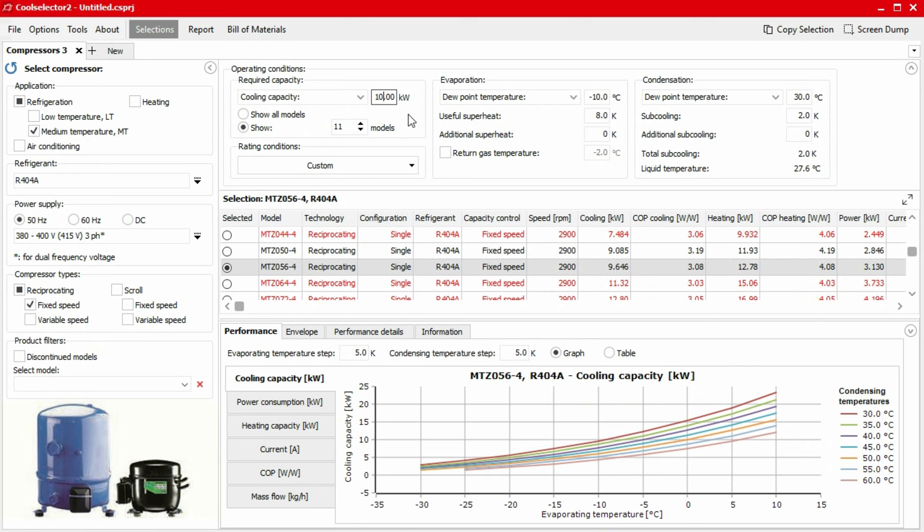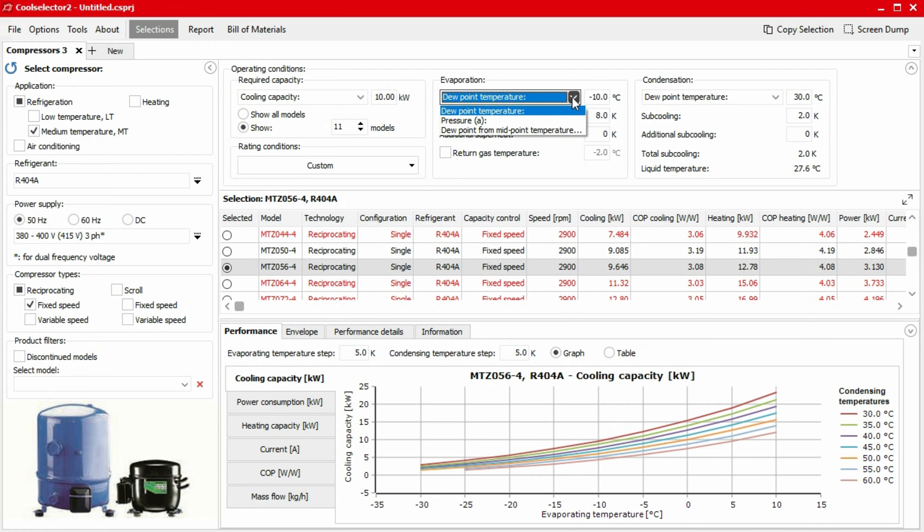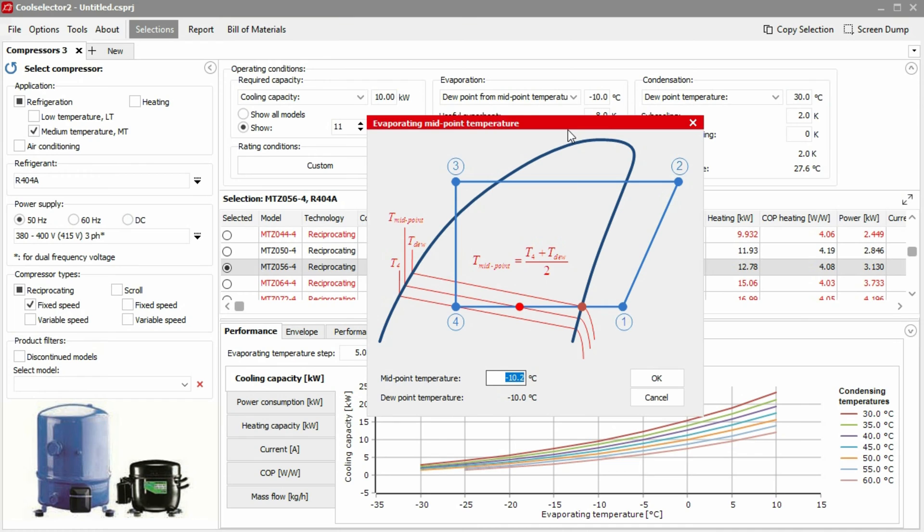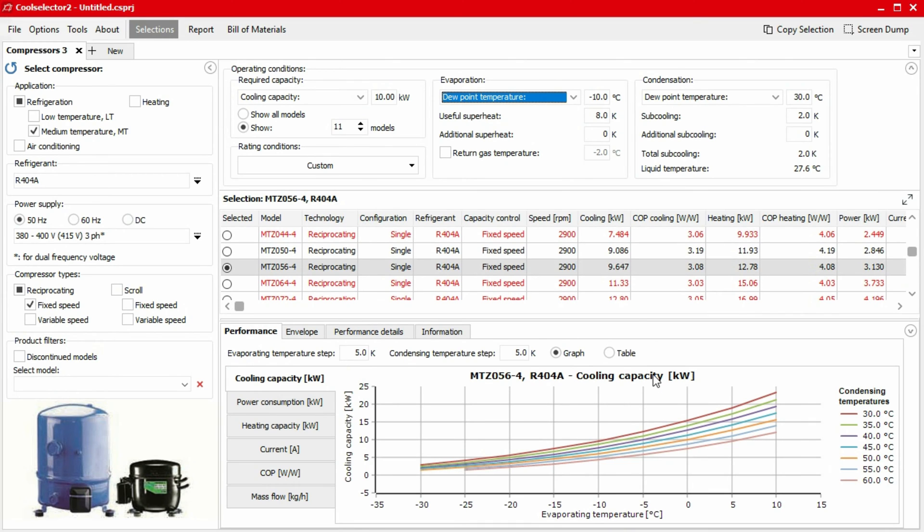Then we need to set the evaporator conditions. Since R404A is a glide refrigerant, we need to choose the reference point for the evaporator and condenser temperatures. For the evaporator, we want to use the midpoint temperature. So we choose this option and then input our midpoint temperature value in the pop-up. CoolSelector 2 automatically calculates the dew point based on the input. We can also input the useful superheat in the evaporator and any additional superheat before the compressor.